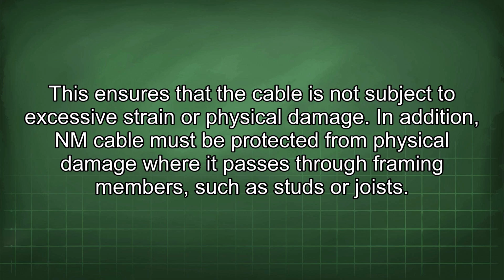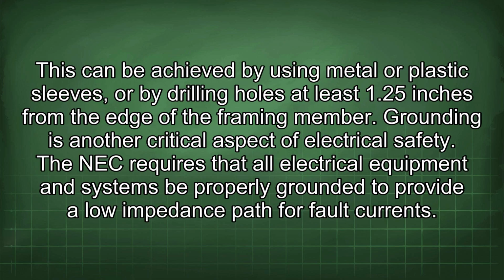In addition, NM cable must be protected from physical damage where it passes through framing members, such as studs or joists. This can be achieved by using metal or plastic sleeves, or by drilling holes at least 1.25 inches from the edge of the framing member.